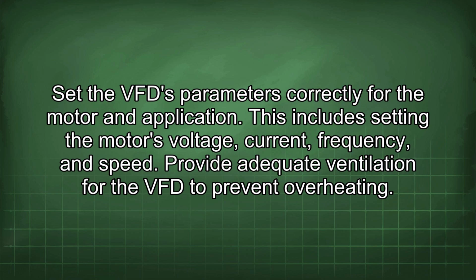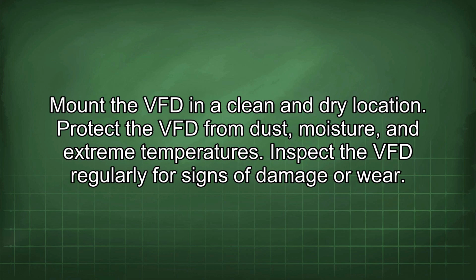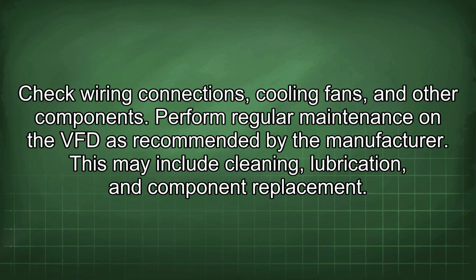Set the VFD parameters correctly for the motor and application. This includes setting the motor's voltage, current, frequency, and speed. Provide adequate ventilation for the VFD to prevent overheating. Mount the VFD in a clean and dry location. Protect the VFD from dust, moisture, and extreme temperatures. Inspect the VFD regularly for signs of damage or wear. Check wiring connections, cooling fans, and other components. Perform regular maintenance on the VFD as recommended by the manufacturer. This may include cleaning, lubrication, and component replacement.